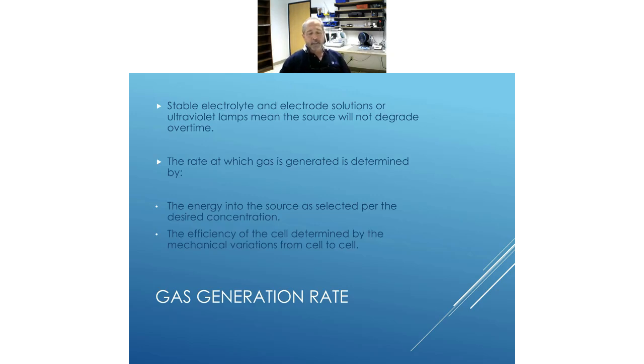The other nice thing about gas generation is it's got a fixed determination. So the energy into the source, either electrochemically or through the excitation of the lamp, gives you a fixed amount of molecules of gas out. We blend that with a carrier gas, which is normally the ambient air in the room, and that gives us a certain amount of gas out. And the beauty about that is you can change it.